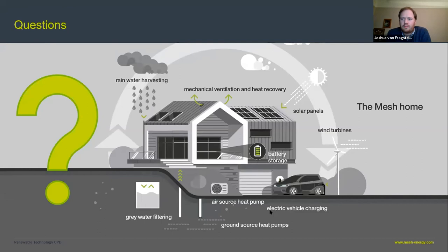The reason being that the efficiency of heat pumps, for example, will vary with flow temperature. So if you have a building which is optimized for a heat pump, then it will pay back a lot more quickly than a system where you're retrofitting to a heat emitter system that was originally designed for a boiler and therefore much higher flow temperatures, where you'll get a lower coefficient of performance, and hence the savings are much smaller. But that's the kind of thing we look at in the feasibility at stage one, stage two. That's why we don't always have a one size fits all scenario, because it is different for every building.